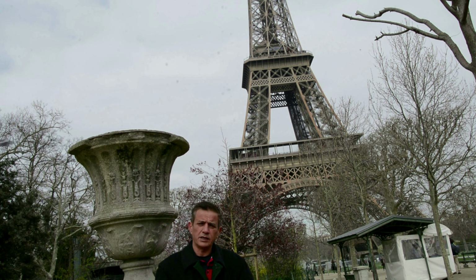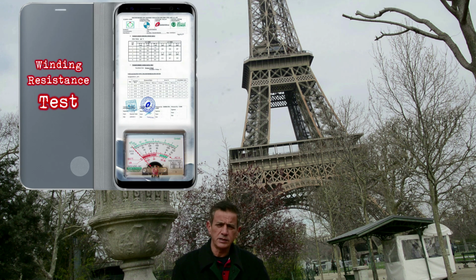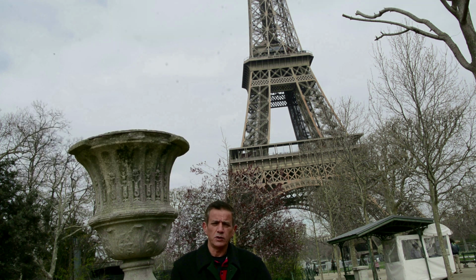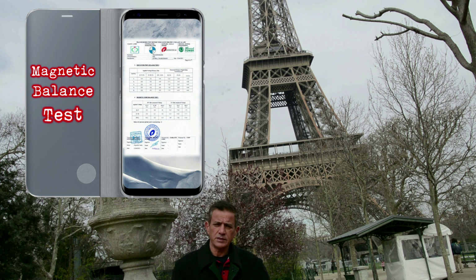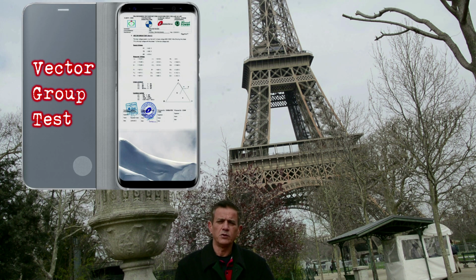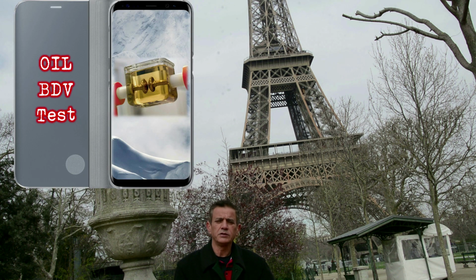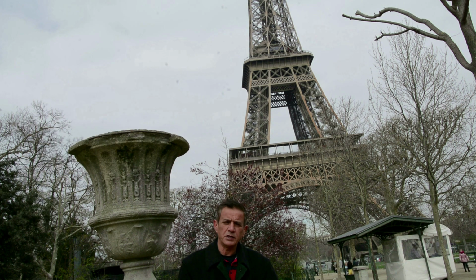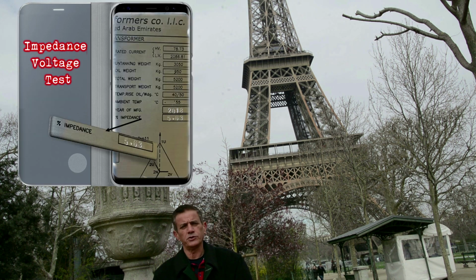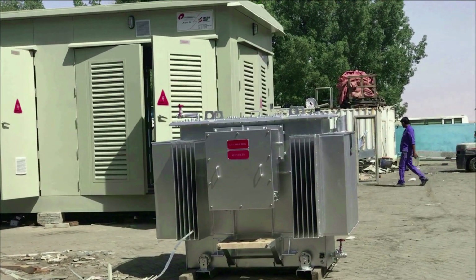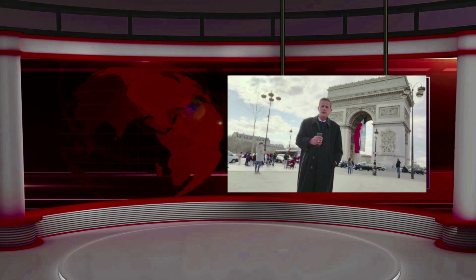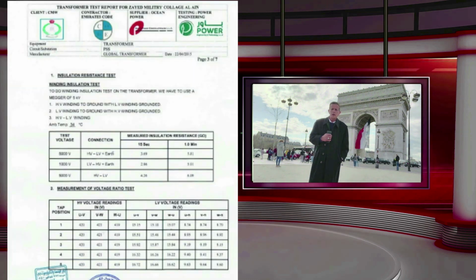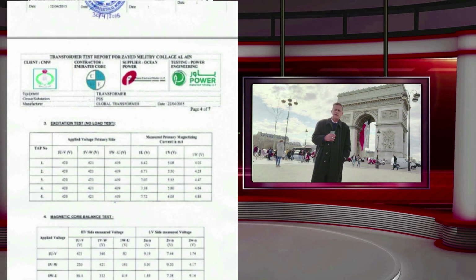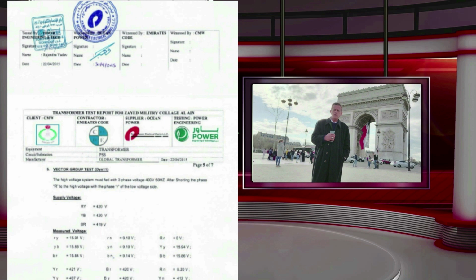Some of the tests carried out on transformers are the winding resistance test, insulation test, magnetic balance test, vector group test, oil breakdown voltage test, high voltage test, basic impulse level test, impedance voltage test, or the percentage impedance, and so on. We will be discussing these tests from the practical point of view. We will see the results taken from the factory or from the site with practical figures.